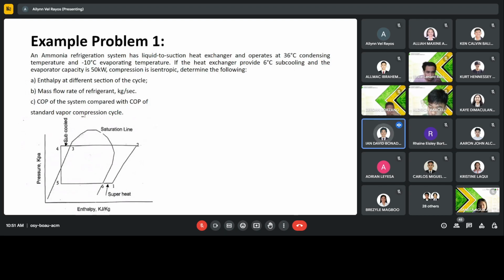An ammonia refrigeration system has a liquid suction heat exchanger and operates at 36 degrees Celsius condensing temperature and -10 degrees Celsius evaporating temperature. If the heat exchanger provides 6 degrees temperature subcooling and the evaporator capacity is 50 kilowatts, and compression is isentropic, determine the following: A, enthalpy at different sections of the cycle; B, mass flow rate of refrigerant in kilogram per second; C, COP of the system compared with COP of the standard vapor compression cycle.